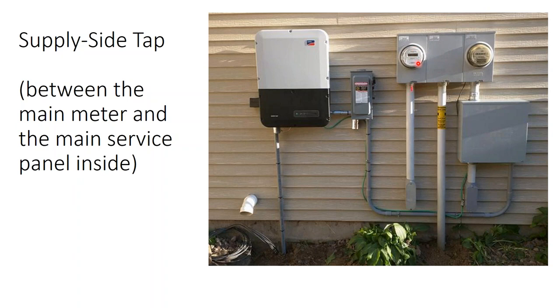This is a completely separate electric service for an independent heat pump, so that's really not part of the project. This is the customer's meter. What happens is we're interconnecting the solar array. This is where the customer's power goes into their building, into their service panel that's in the basement of their home. We're not connecting onto the customer's service panel, which is inside the building. We're connecting between the service panel and the customer meter. So we output electricity, and it intercepts here, and whatever load is not sucked in by the service panel gets backfed into the grid.